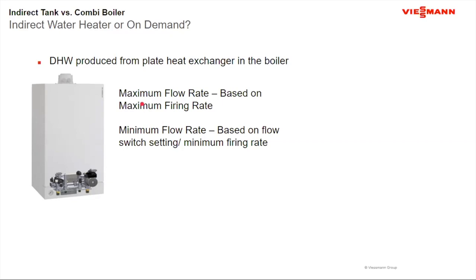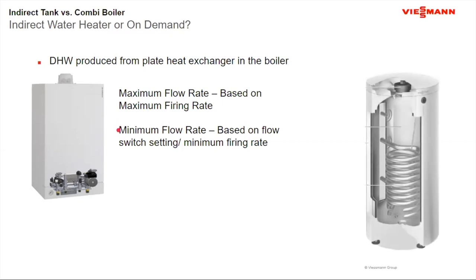And again, based on this, typically when I do domestic hot water through a combi, particularly when I'm looking for the higher inputs for maximum flow, I start to look for a much higher turndown ratio to get where I need to be for my minimum flow rate. Now, when I start to look at the storage water heater, I have a tank water heater here.